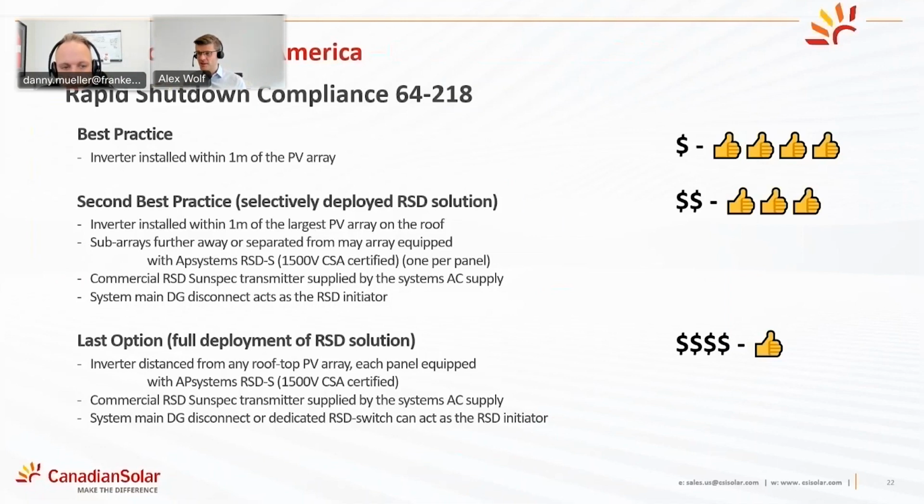Coming back to Dave's question, how maybe SolarEdge system on the commercial scale can be replaced. That's exactly how you want to do it. That you don't have an optimizer for every panel. The first step would be, can you place the inverter on the roof? Yes or no? If you can, your best bet, lowest cost, highest reliability, and easiest installation, because you literally don't have any panel level components.